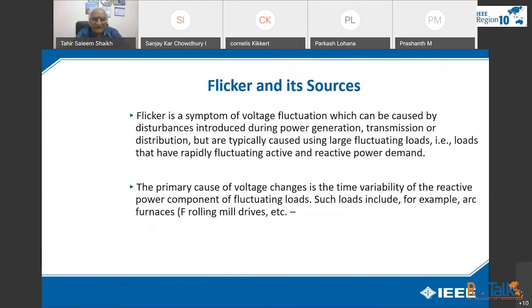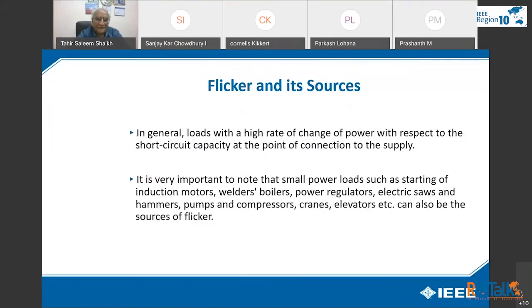Flicker is a symptom of voltage fluctuation, which can be caused by disturbances introduced during power generation, transmission, or distribution, but is typically caused by large fluctuating loads, or loads that have rapidly fluctuating active or reactive power demand. The primary cause of the voltage changes is the time variability of the reactive power components of the fluctuating loads. Such loads include, for example, arc furnaces, rolling mill drives, etc. In general, loads with a higher rate of change of power with respect to the short circuit capacity at the point of connection to the supply are the problem. It is very important to note that small power loads such as starting of induction motors, welders, boilers, power regulators, electrical saws and hammers, pumps and compressor cranes can also be the source of flicker whenever transients occur.